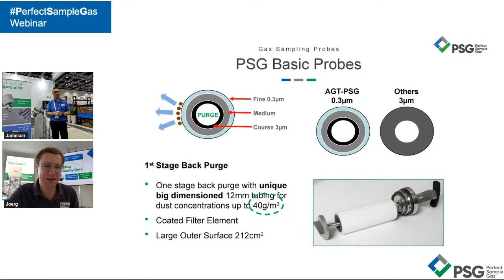What do we need to consider from your side regarding pressure reduction and these kinds of things? Yeah, I think that almost every customer, when they do a back purge, would prefer that the back purging air does not go downstream to the gas analyzer. At the same time, we want to pressurize the back purge. Therefore, it is important to have a pressure reduction valve at the sample outlet, so that when we do a back purge, we want it to be accumulated in the sample probe body itself, to deliver the effective purge.